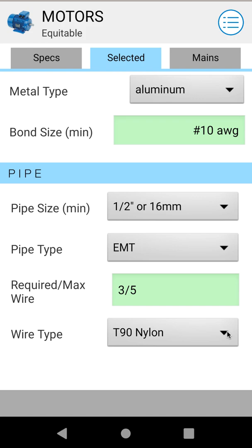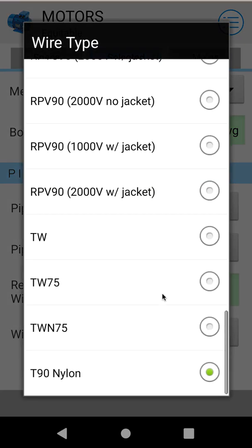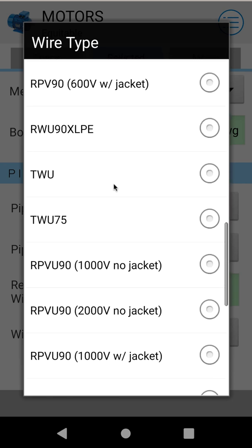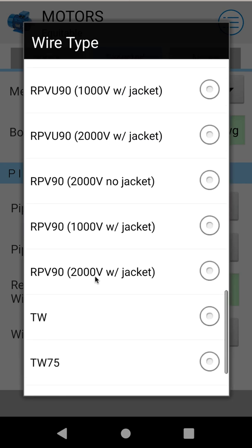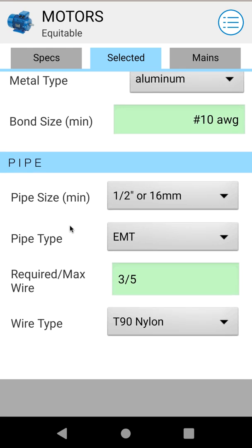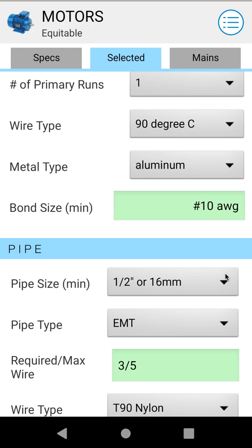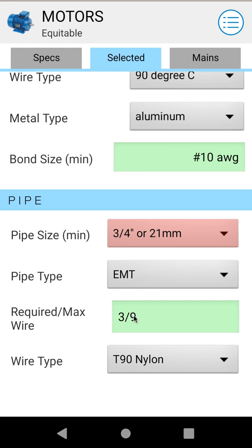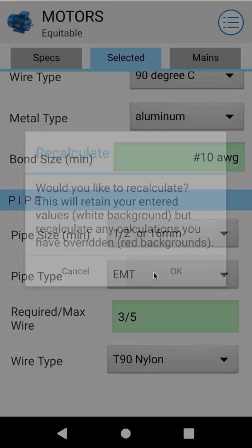Your last selection is what type of wire you're pulling in. Right now we're at T-90 nylon, but you can choose from a whole variety of wires included in your code book, and this will affect your pipe fill. For example, if I go to an RPV 90 with jacket, now I can only fit three wires in a half inch conduit, as opposed to the five we had with T-90. You can also adjust your pipe size — for example, upsizing to three quarter inch gives a lot more space, fitting nine wires. Like wire size, it'll turn red to indicate a modified result, and you can hit recalculate to go back to the default.